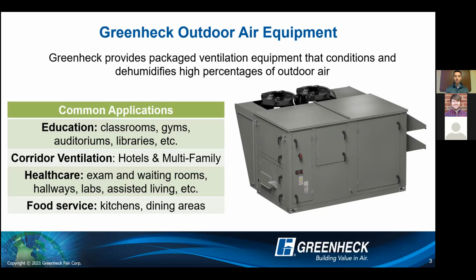So common applications that we're really serving with this type of equipment, a lot of education facilities, about 65% of Greenheck's Doas work goes to education facilities like classrooms, gymnasiums, auditoriums, things like that. I do a lot of corridor ventilation with Doas units, so hotels, multifamily establishments. Also get into healthcare and food service with this type of equipment as well. So anytime that you're really thinking about bringing in high percentages of outside air where we need to worry about comfort cooling, the occupants in the space to make sure that they are happy, they are comfortable, that's where you're going to want to apply units like the Greenheck Doas equipment.